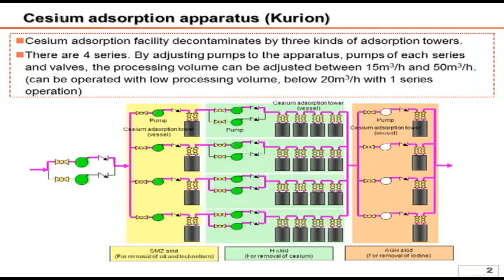The total capacity of 50 cubic meters per hour is equivalent to 1,200 tons per day. Looking at each series, the first portion of the cesium adsorption tower is called the SMZ skid, which contains a float stone and removes oil and impurities such as technetium. The next portion with the four vessels is called the H skid, which adsorbs cesium. The last is the AGH skid, which removes iodine.